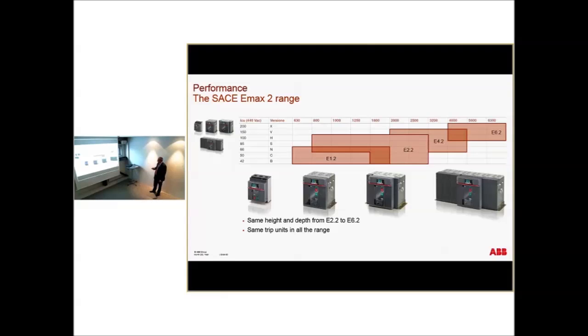General characteristics is we have the same height and the same depth for the whole range, same releases. Basically, we have 4 different sizes, no more 5 sizes. This is a small one. It's slightly smaller in depth and height compared to the other one. It goes up to 1600 amps. Then you have a 2500 amps, the second one, 4000 amps, and 6300 amps.